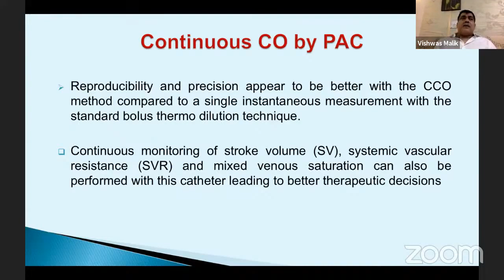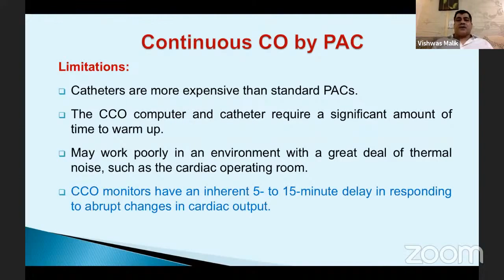However, nothing is foolproof in this world, neither is CCO. The catheters are more expensive than standard PACs, around double the cost. The CCO computer and catheter require a significant amount of time to warm up. They may work poorly in an environment with too much thermal noise in the background, such as a cardiac operating room with cardiopulmonary bypass. And CCO monitors have an inherent 5 to 15 minute delay in responding to abrupt changes in cardiac output. So when we need them most, they might falter.